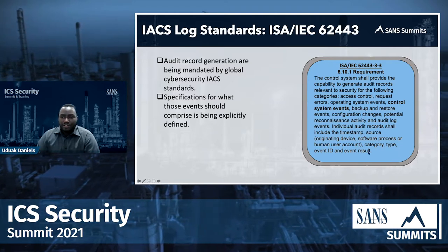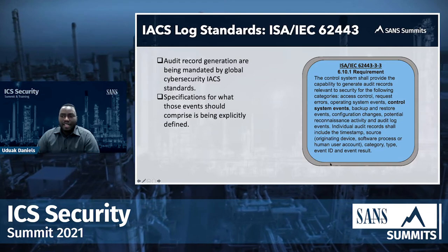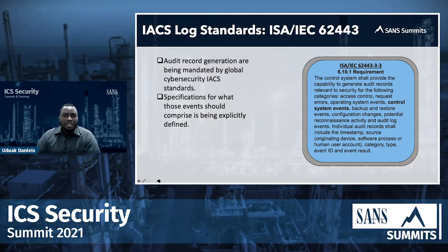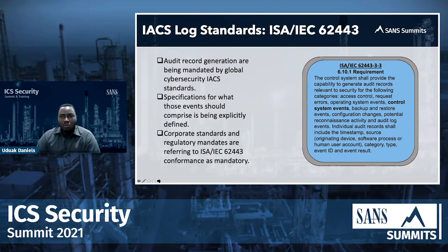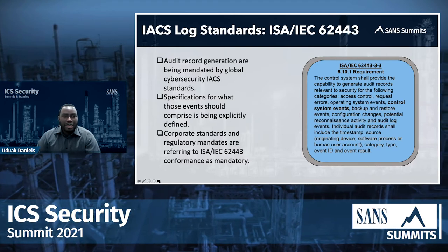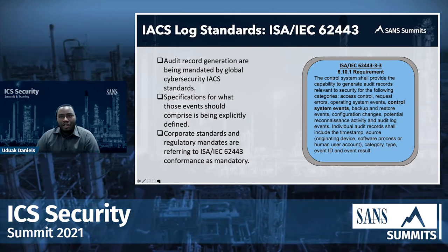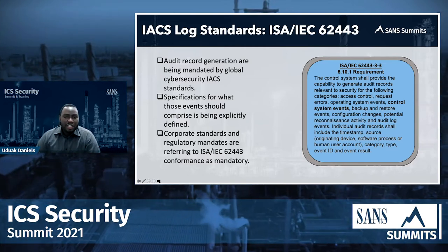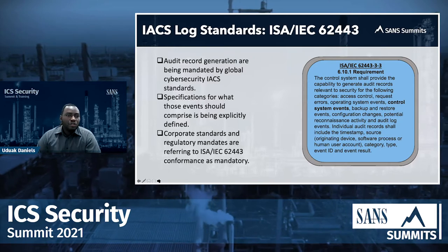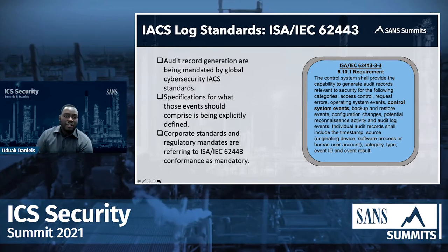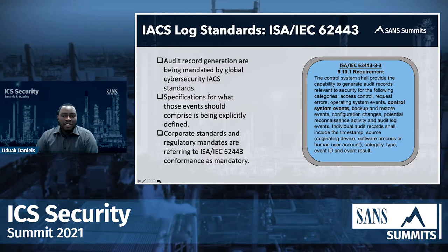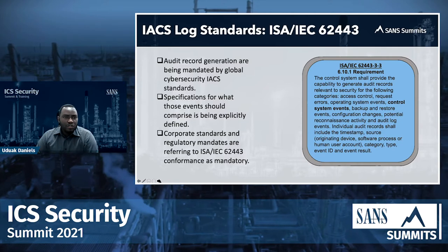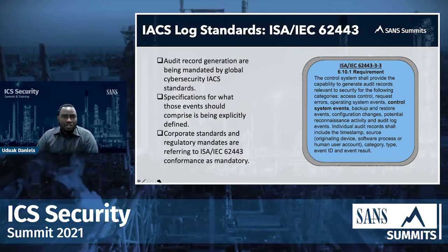Everything is driven by some policy, standard, or procedure. IEC 62443 has a requirement — specifically SR 6.1 — which specifies that control system events have to be included as part of the events considered for a robust security monitoring program. The specification defines category, event types, event results, and originating device. Corporate standards and regulatory mandates reference 62443 as the standard for industrial automation and control systems.